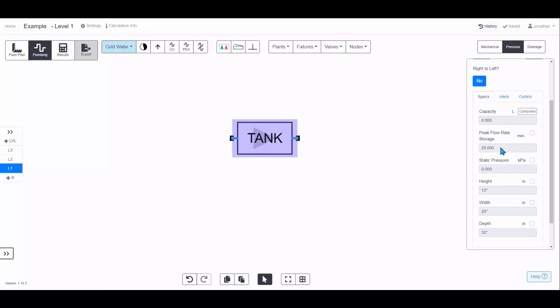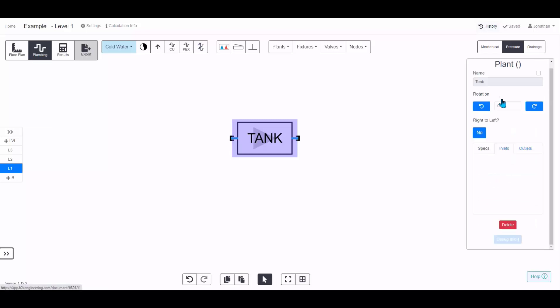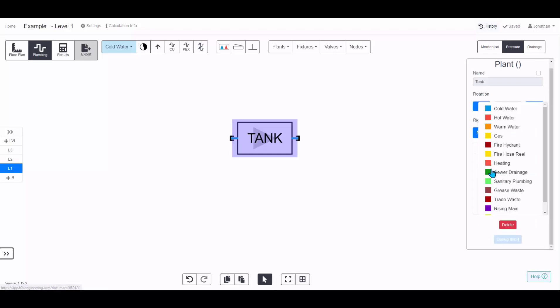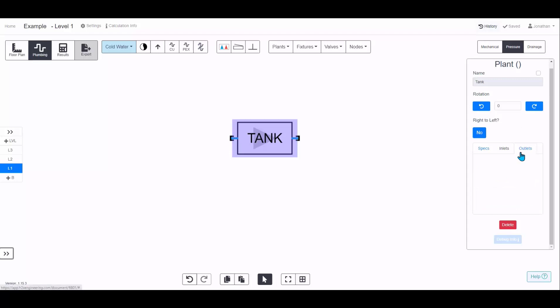You can either enter a capacity or let it calculate based on storage of the peak flow rate. The static pressure defaults to zero, but if you have a couple of meters of water you could get that close to 20 kPa. On the inlets it shows what systems to connect and at what height, and the same for the outlets.